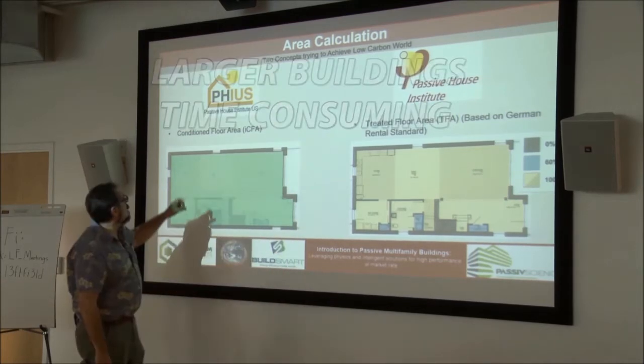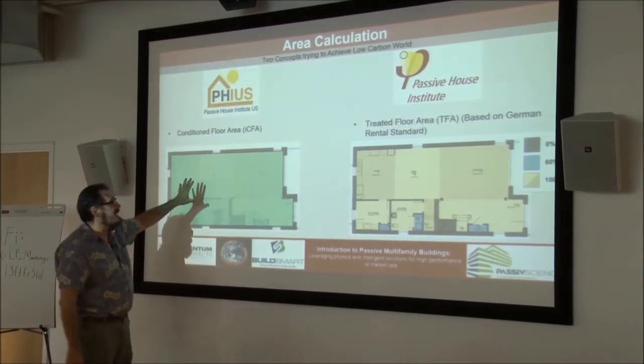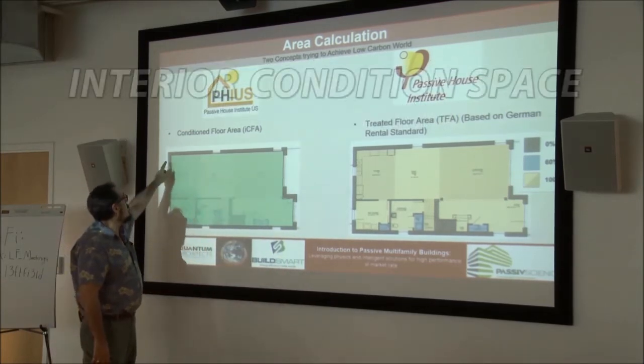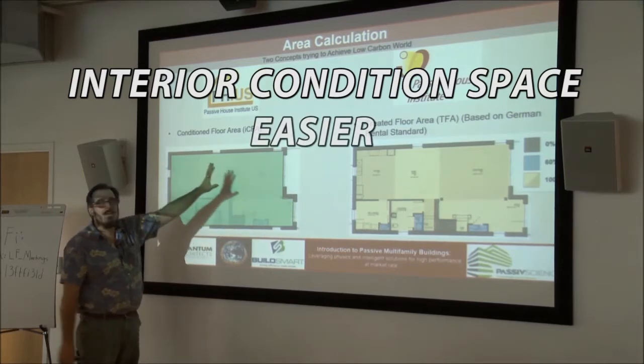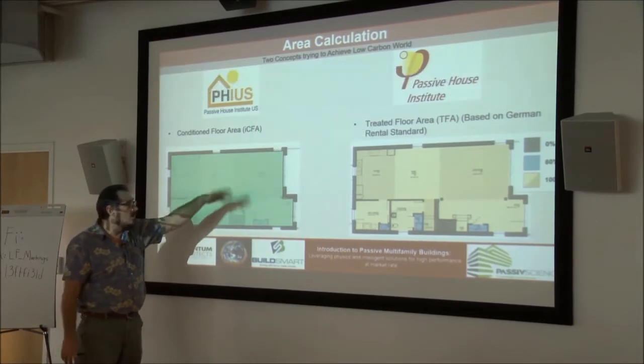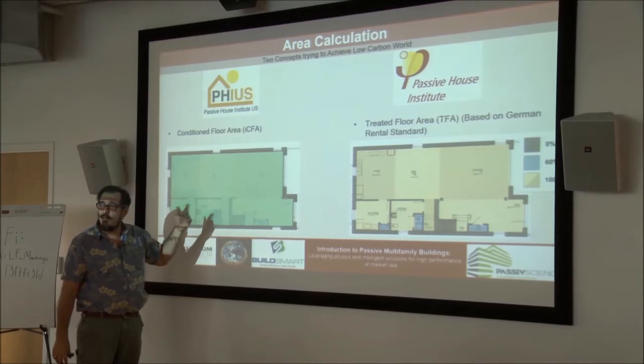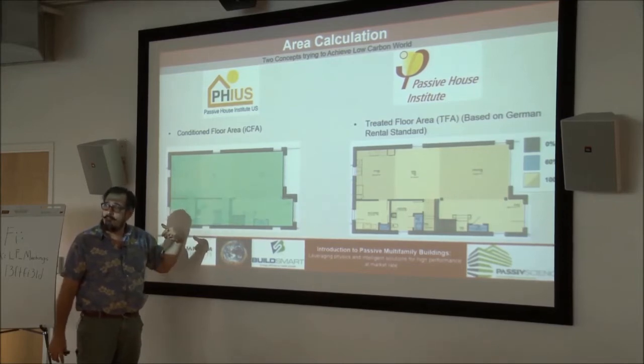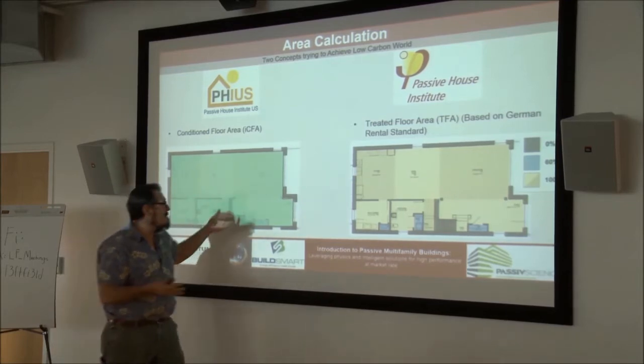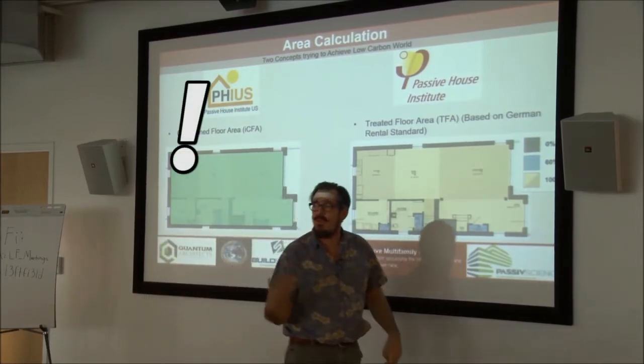In the PHI standard, it's a similar standard but they're taking interior conditioned space, so it's a much easier calculation for people to make. It's just the total interior from the inside of the thermal envelope — that total interior conditioned area. It doesn't really matter whether you use this one or that one, as long as you know which one the software takes and you put that in.